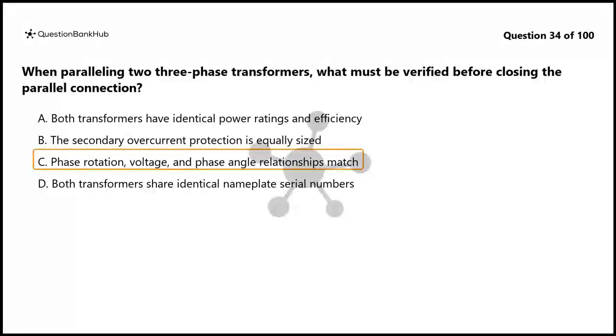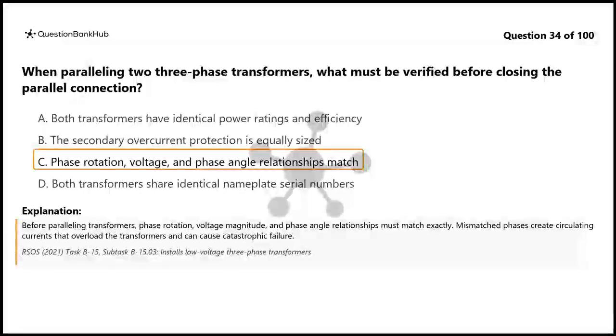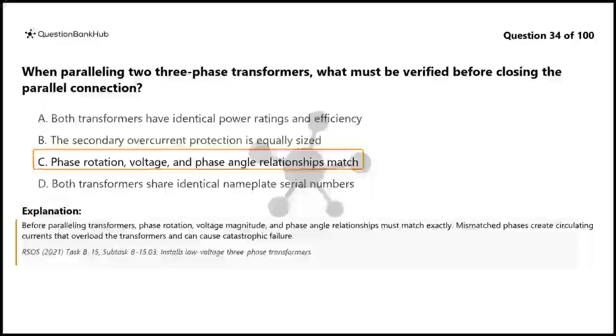The correct answer is C. Phase rotation, voltage, and phase angle relationships match. Before paralleling transformers, phase rotation, voltage magnitude, and phase angle relationships must match exactly. Mismatched phases create circulating currents that overload the transformers and can cause catastrophic failure.